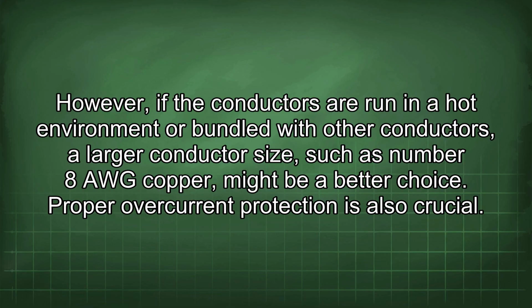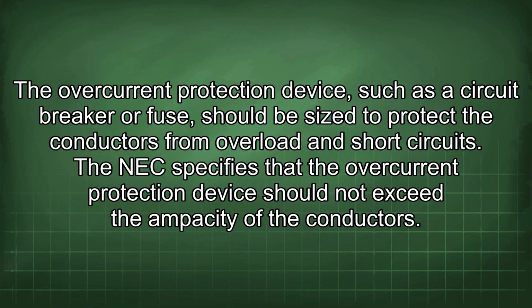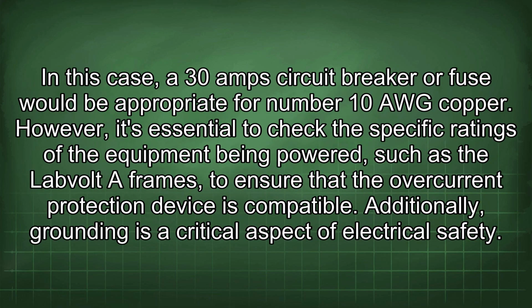Proper overcurrent protection is also crucial. The overcurrent protection device, such as a circuit breaker or fuse, should be sized to protect the conductors from overload and short circuits. The NEC specifies that the overcurrent protection device should not exceed the ampacity of the conductors. In this case, a 30 amp circuit breaker or fuse would be appropriate for number 10 AWG copper.